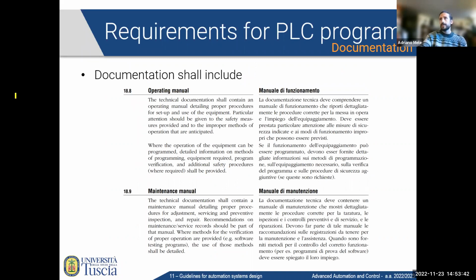You also need to provide an operating manual. The technical documentation shall contain an operating manual detailing proper procedures for setup and use of the equipment, with particular attention to safety measures.